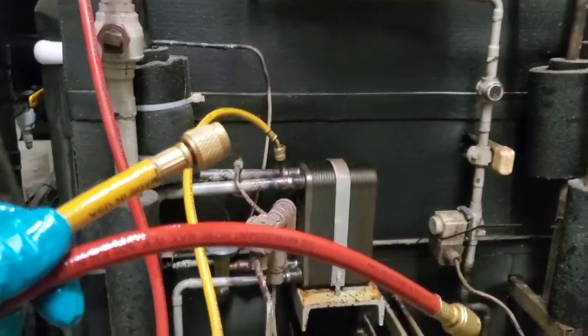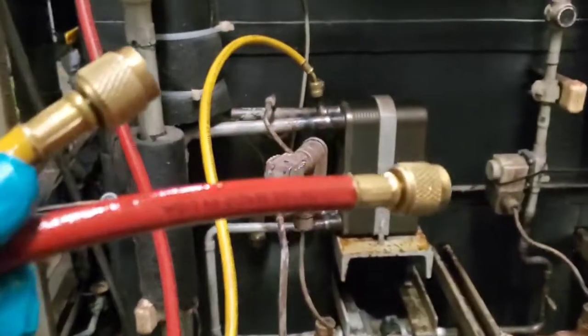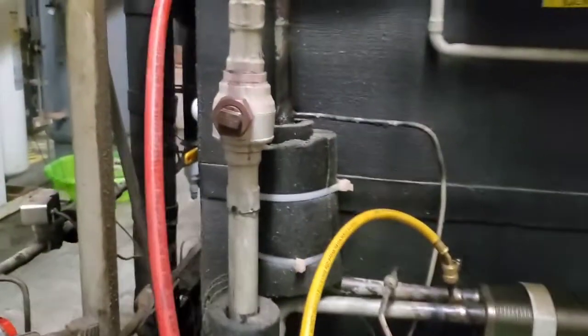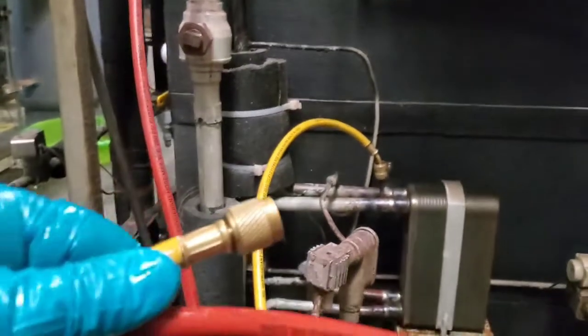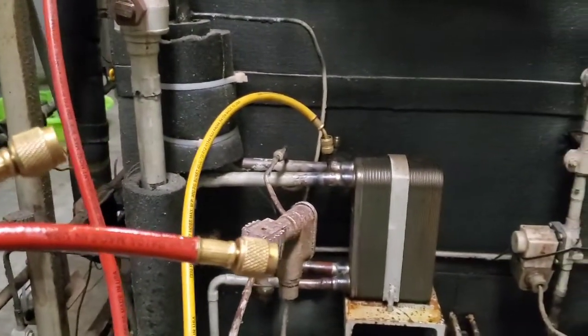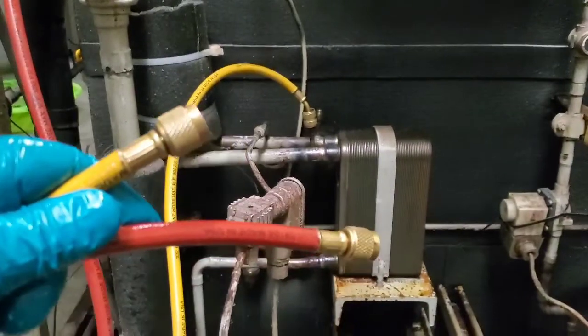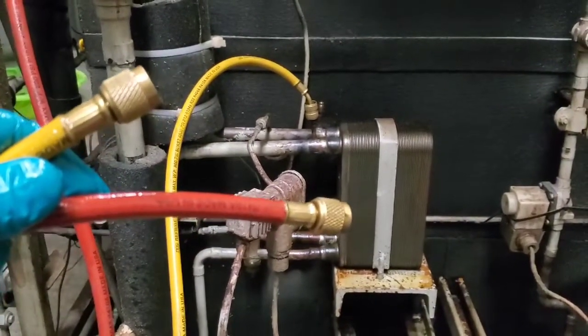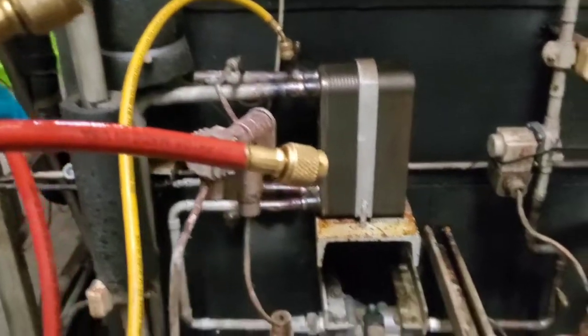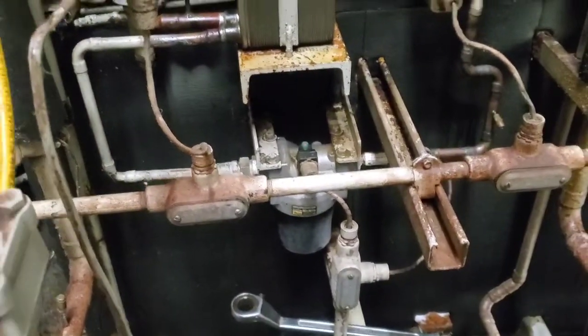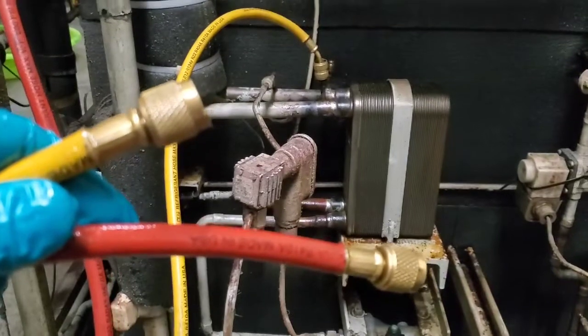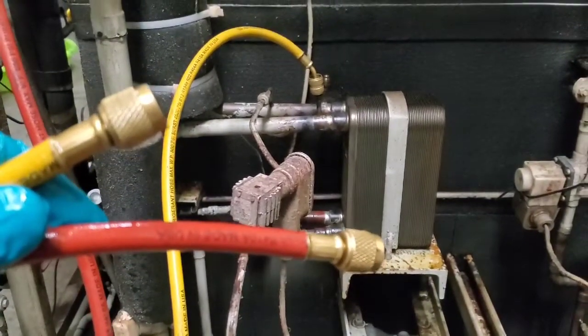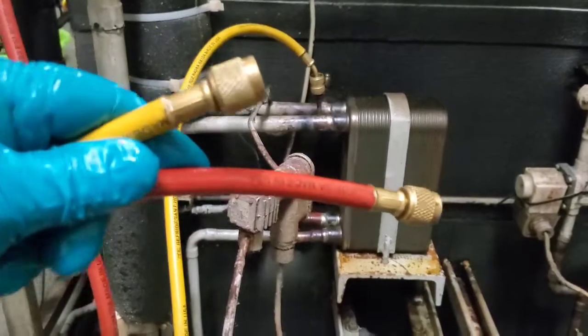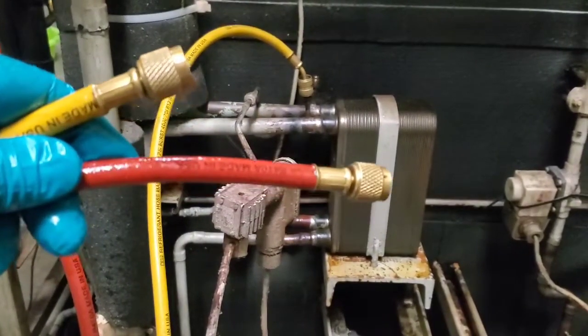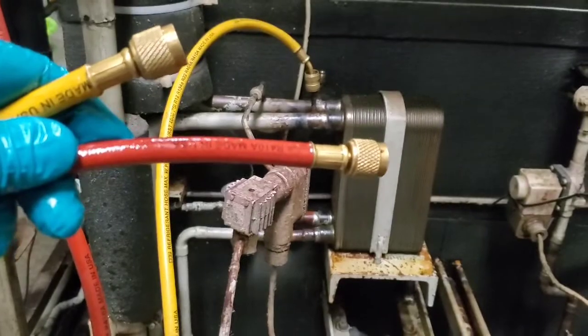All right, we've gotten all the pressure out of these lines, and I got my hoses that are connected to them open. The reason why I'm doing that is that the isolation valves like that one and some of the other ones that I'm using leak by just a little bit. And so if we don't leave a place for this piping section to be vented, we're just going to build up pressure, and any pressure over about 1 or 2 PSI when you're trying to deal with oil will just spray it everywhere. So even 5 PSI will make an absolute mess. So I'm avoiding that by leaving these open, and of course we're going to pull a vacuum when we're done, so we'll get all the air out.